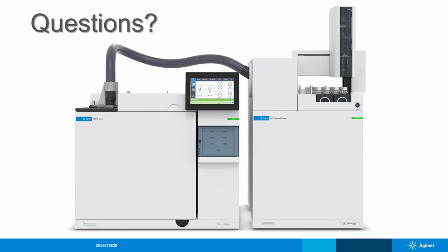Yeah, I would similarly not recommend reusing it. One additional aspect that would be concerning as well is potentially the physical robustness of the vial. Given that if you are crimping that vial, you're applying a decent amount of pressure to it, and then you've also thermally cycled it, you would not want to potentially have that vial rupture either on the benchtop when you first crimp it, or even worse in the oven itself, forcing you to have to open up the instrument and clean whatever was in the vial out.